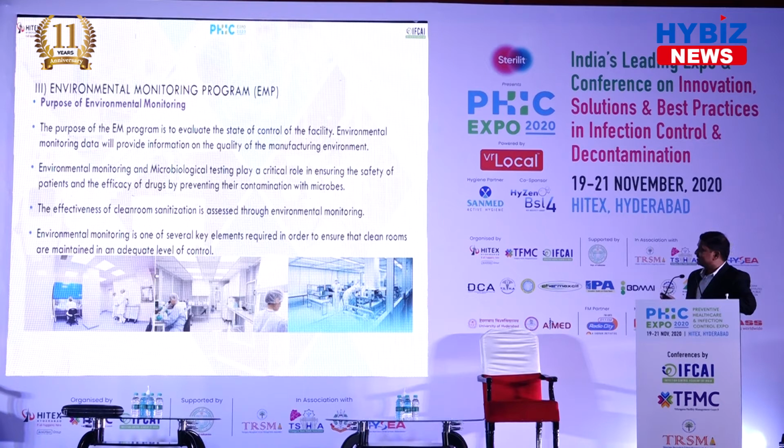One more purpose is that environmental monitoring is one of the several key elements required to ensure that clean rooms are maintained in an adequate state of control. And clean room monitoring, or environmental monitoring, is a process to evaluate the quality of the clean room, the quality of the area, not the quality of the product.